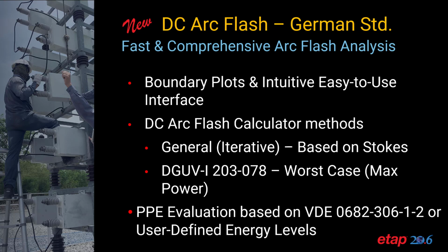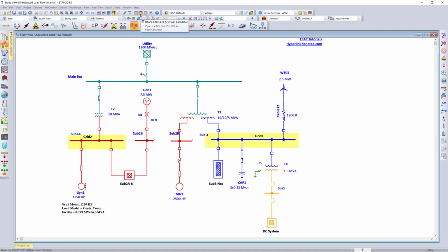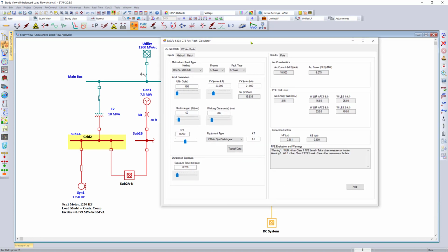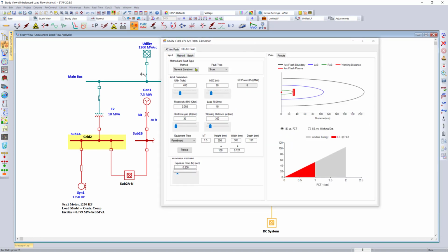Arc flash analysis is not only a North American requirement, it is a global analysis requirement. In several EU countries, the analysis is performed using DGUV standards. ETAP 20.6 provides you with the capability to determine the arc energy for DC electrical installations based on 2 methods. The first one is called the general or the iterative method, which is very similar to the NFPA 70E rigorous calculation method, or otherwise known in ETAP as the Stokes and Oppenlander method, but with some variations in the gradients and anode and cathode voltage coefficients.